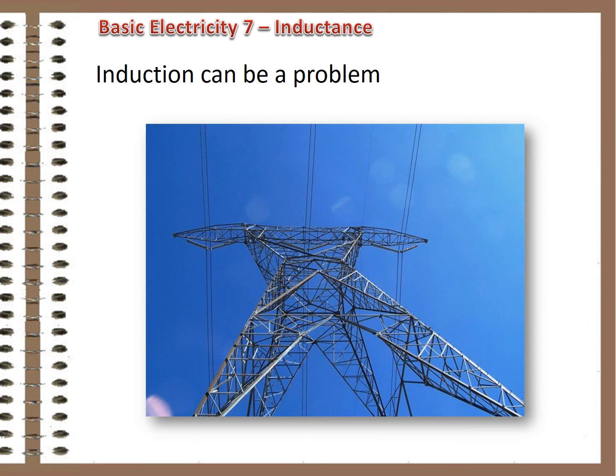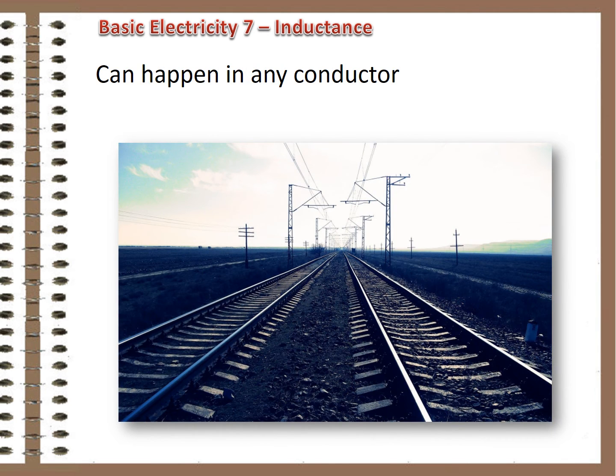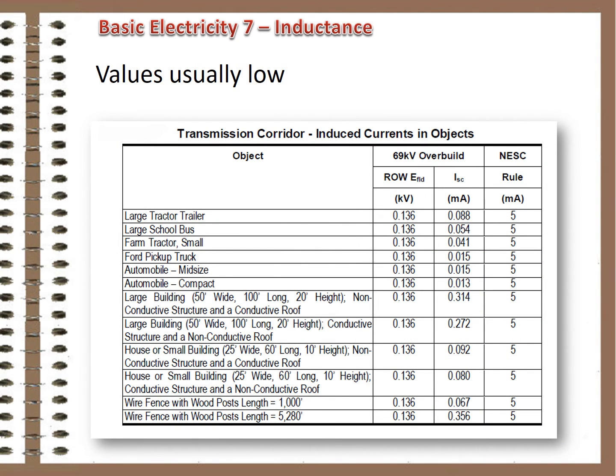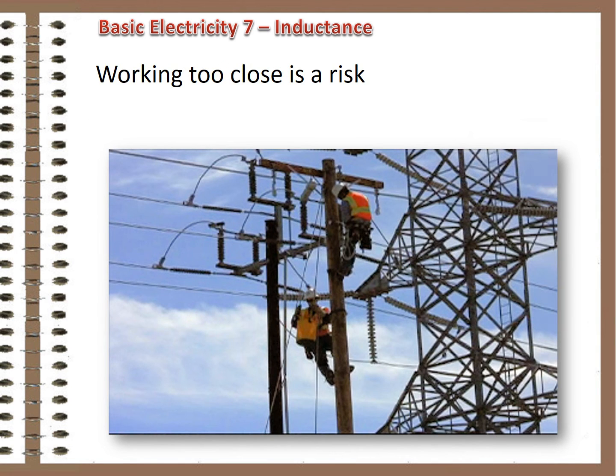But those same properties, when occurring in high-voltage electrical systems, cause problems. The first one involves safety. Is a railroad rail a conductor? Do electrical lines run parallel to railroad tracks sometimes? Is voltage induced in the rail? You bet it is. Wire fences, metal buildings, rain gutters, vehicles — all can have voltage induced in them when exposed to the moving magnetic field around an AC-carrying conductor. Generally, the voltages and resulting currents are very low, well below safety thresholds. Distance is your friend here, as the strength of the magnetic and electric fields diminish very rapidly as you move away. But by the same token, they gain strength rapidly as you move closer. And therein lies the danger.